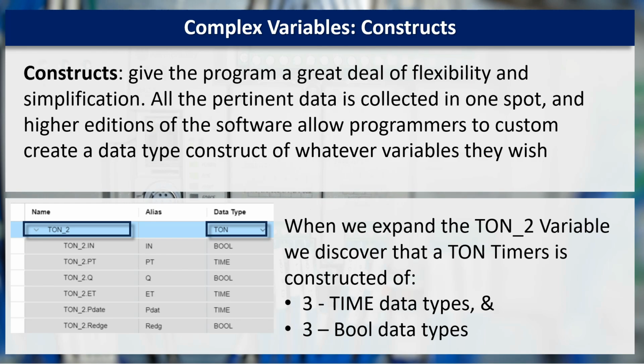Constructs give the programmer a great deal of flexibility and simplification. All the pertinent data is collected in one spot. And higher editions of the software allow programmers to custom create a data type construct of whatever variables they wish. When we expand the TON_2 variable, we discover that a TON timer is constructed of 3 time data types and 3 bool data types.